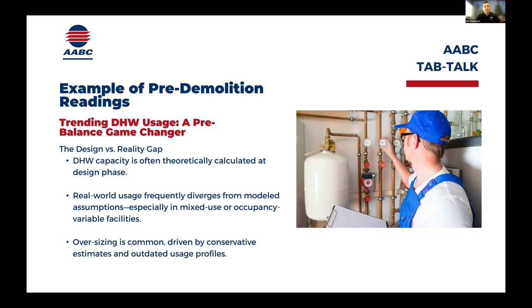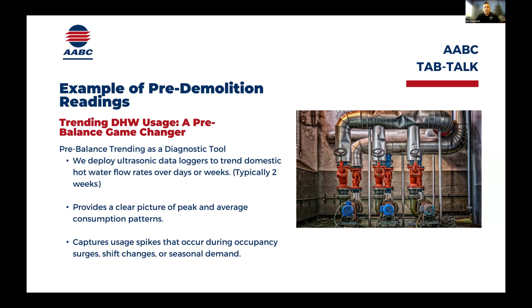So what they've had us do is come trend the heating hot water system for two weeks with an ultrasonic meter and data loggers. We can look at peaks, average consumption, all of those things. What we've found is that a lot of these boilers and heat exchangers were 30 to 40% oversized because they were putting in safety factors - they didn't know what the actual consumption was. Now we have the ability, with the system operating and people in the building, to look at real data, and they're able to resize these boilers and heat exchangers to the appropriate size, reducing cost in the replacement of the units and equipment, but also energy consumption. They were able to bring down the energy consumption for that heating hot water because we're not oversized anymore.